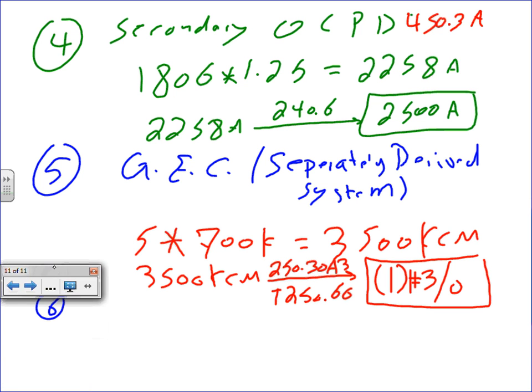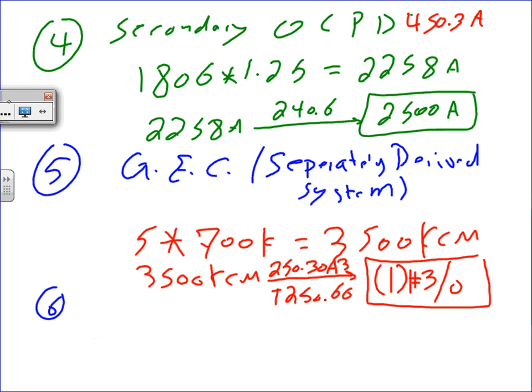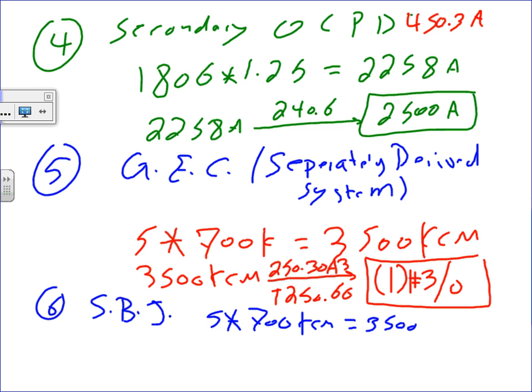Number 6, my friends. Number 6 is the system bonding jumper. You're going to do the same calculation, guys. You're going to take the 5, multiply it by the 700 kcm. It's going to give you 3500 kcm, and this is more than 1100 kcm. If it's more than 1100 kcm, what are you going to do, Brooks? 12.5%. I'm going to take 12.5%. So this is 0.125 times 3500 kcm. My calculation was based on the difference. So what's the answer for this? 12.5% times 3500. How much? 438.